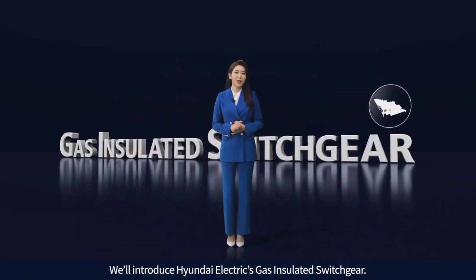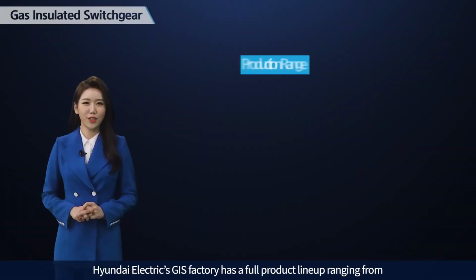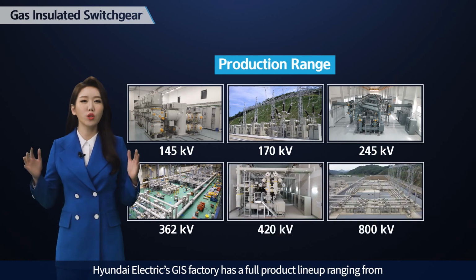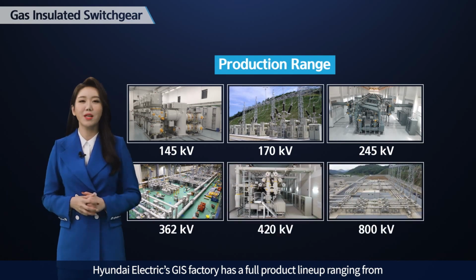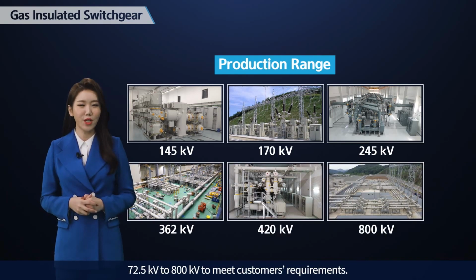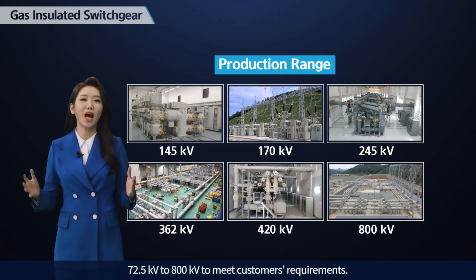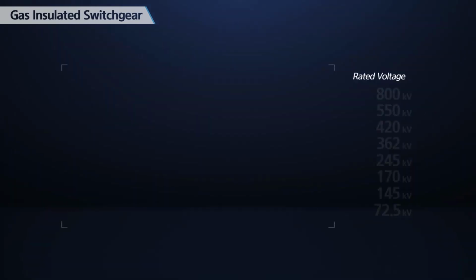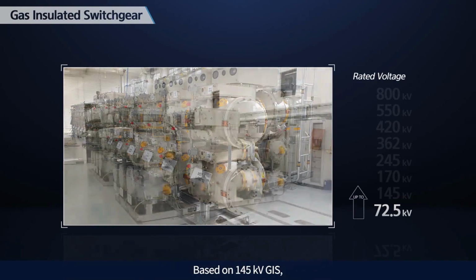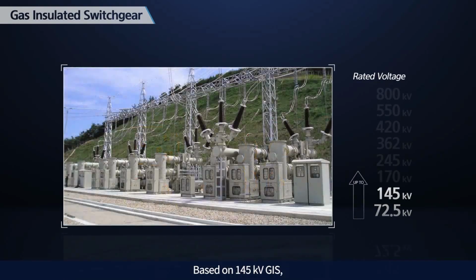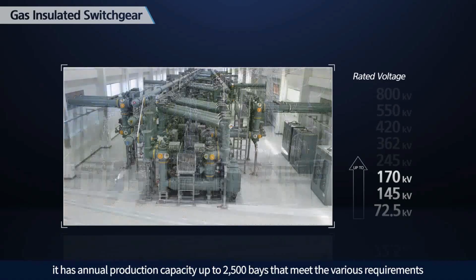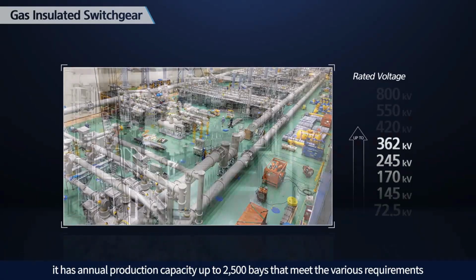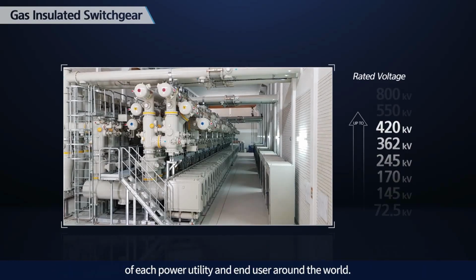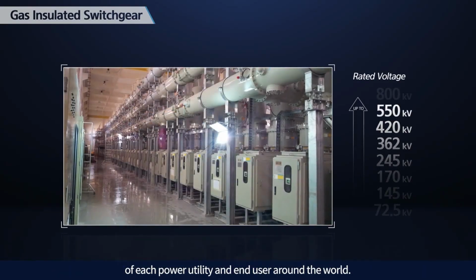We'll introduce Hyundai Electric's gas-insulated switchgear. Hyundai Electric's GIS factory has a full product lineup ranging from 72.5 kV to 800 kV to meet customers' requirements. Based on 145 kV GIS, it has annual production capacity up to 2,500 bays that meet the various requirements of each power utility and end user around the world.